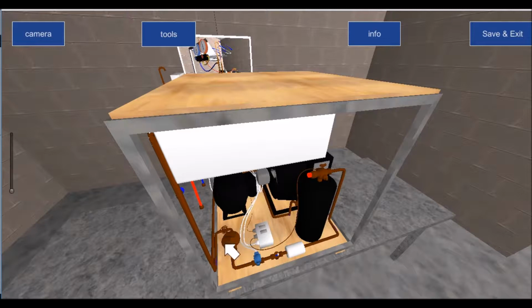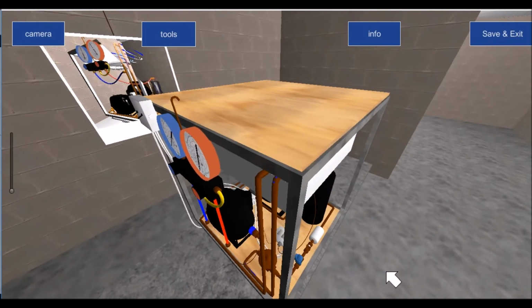Now the metering device can be in the form of a thermostatic expansion valve, such as this here. It can be in the form of a capillary tube. It can be float valves. There can be hand expansion valves and so on. There are various different types of metering devices, and that's why we refer to them simply as metering devices. However, the most common ones on a commercial refrigeration system is the thermostatic expansion valve, or alternatively, more and more these days, it can be an electronic expansion valve. This valve then creates a pressure drop, so it actually converts the high pressure, high temperature subcooled liquid to low pressure, low temperature liquid. That liquid then enters into the evaporator, which is your 4th main component.